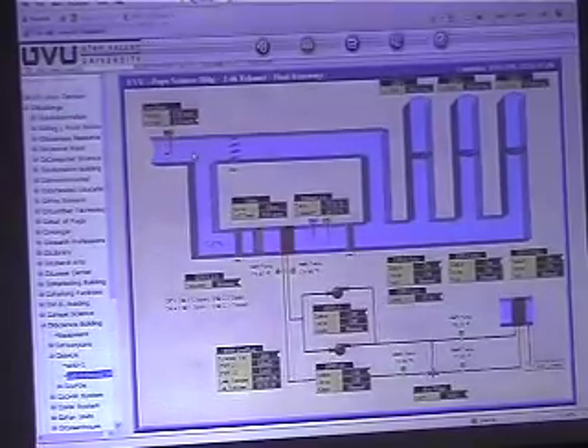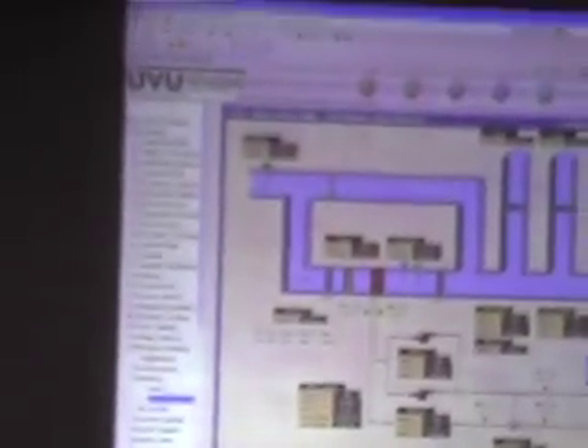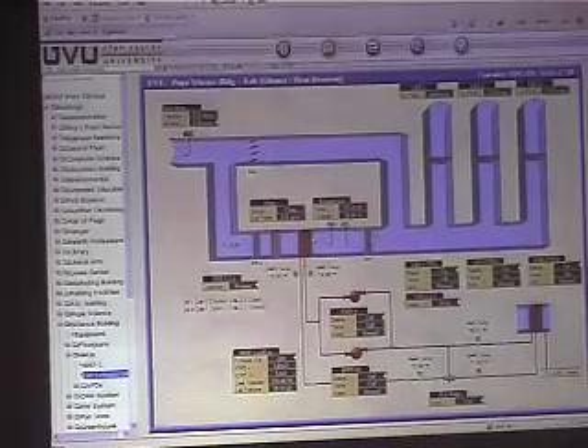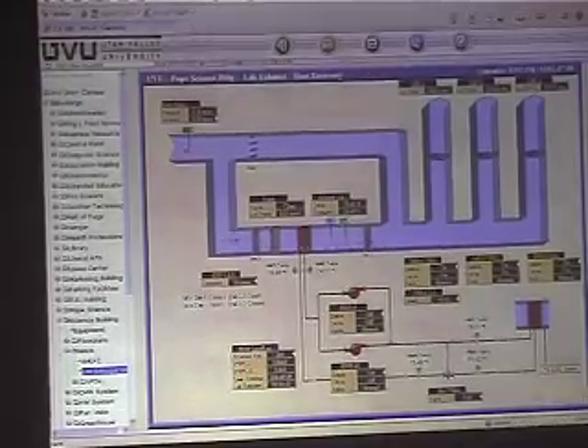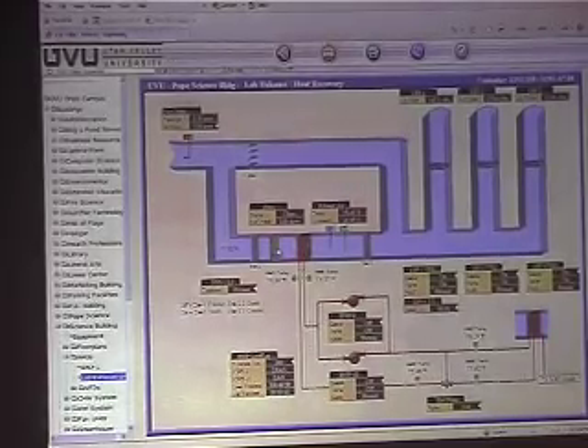And then all the duct from each of those rooms tie together and eventually come back up to this point here. I'll show you when we go up to the penthouse in the walkthrough, but you can see where the return section is, the return chase of the building, and you can see the dedicated duct that comes up and feeds right into that lab exhaust system. So there's a set of dampers here on the lab exhaust. There's a bypass section here, and then there's the section that goes through the coil. The coil section also incorporates the filter section here. So there's dampers on both sides of this section. This is to isolate that off so that when you're doing a filter change, you're not in the exposed airflow.